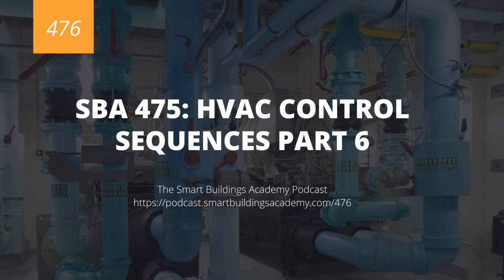Now, via some sort of chilled water flow switch, which is not really clear in this sequence, the chiller is enabled to operate. Via its own microprocessor controls, the chiller is going to operate to maintain a leaving chilled water temperature of 55 degrees adjustable, which, man, that is really high. So that tells me this is most likely dealing with some sort of process load, because 55 degrees, I ideally would not want that controlling spaces and things that have tremendous heat loads. I would be looking more for 42 degrees, but that's just me.